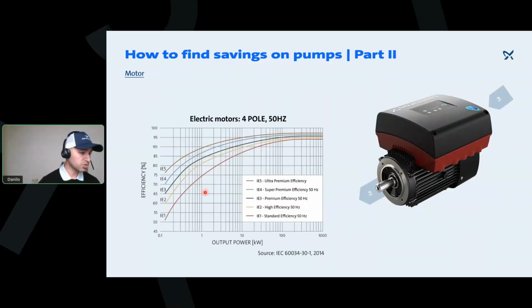You also probably don't want to, because of their efficiency, but also because that little fan which runs together with the shaft is not going to have the same cooling capabilities, and now you're having overheating of your motor, right? So this kind of motor, because of how they operate, being permanent magnet, you can go all the way down to 7%. We actually have a circulator pump that we can bring all the way down to 7% due to how we keep it cooled.